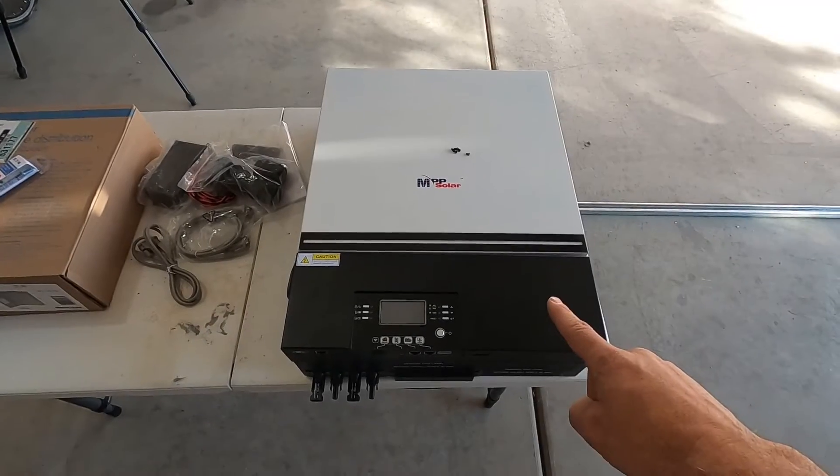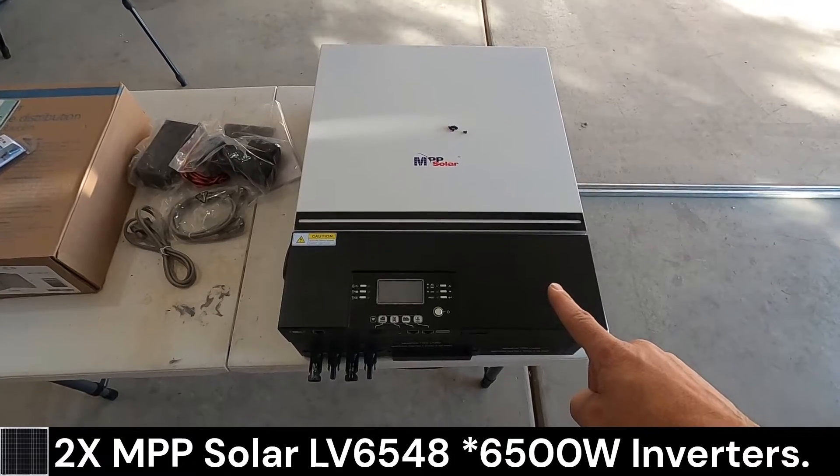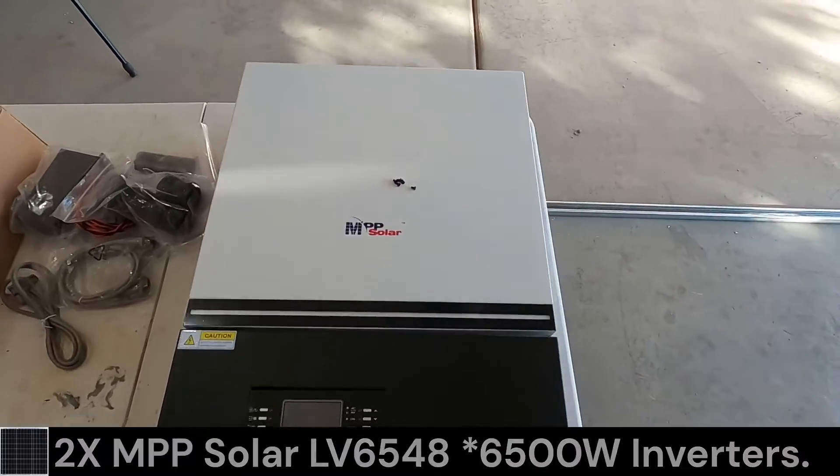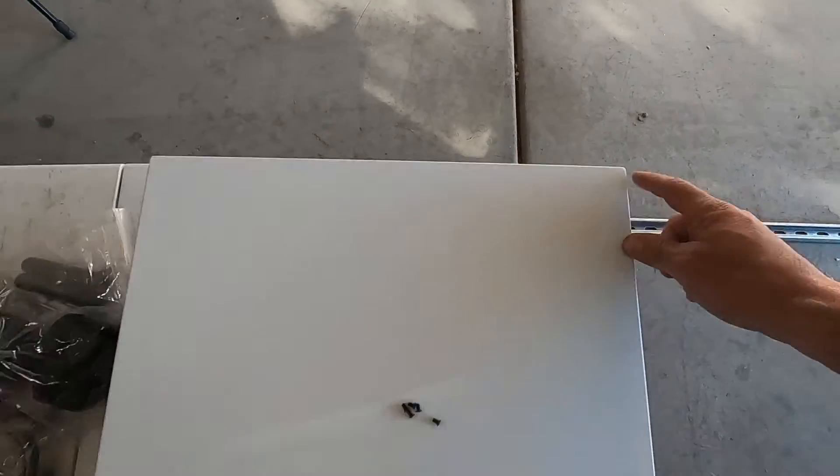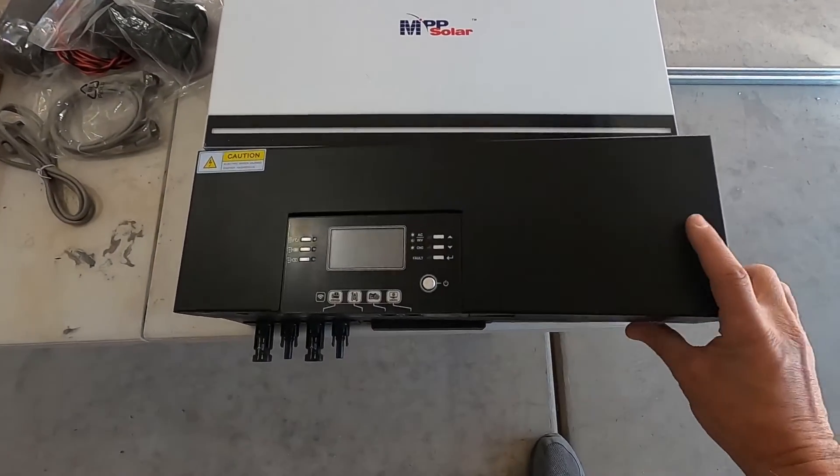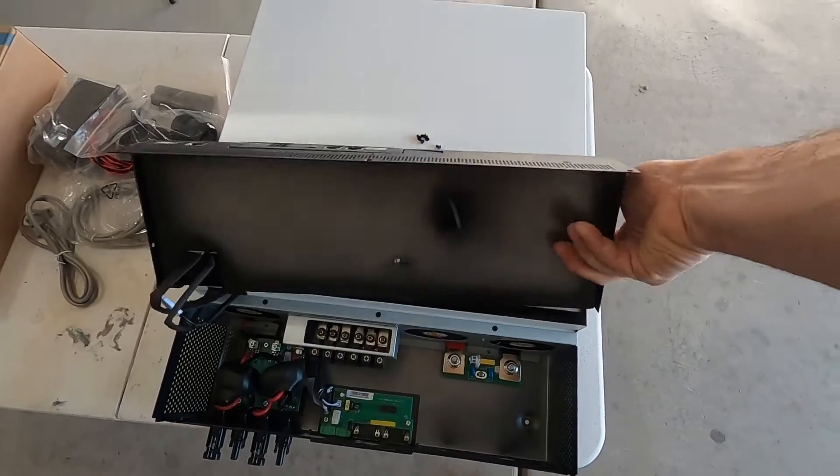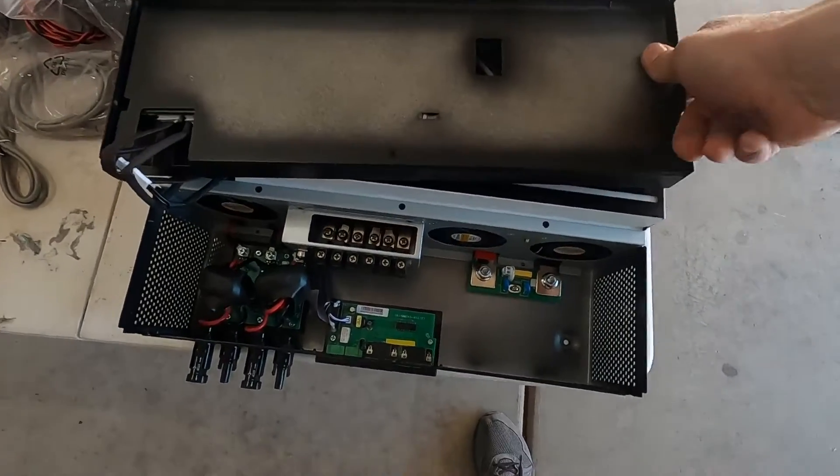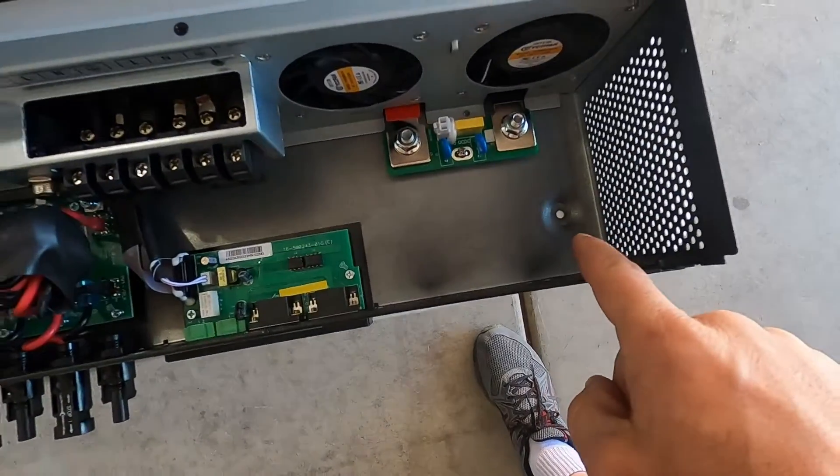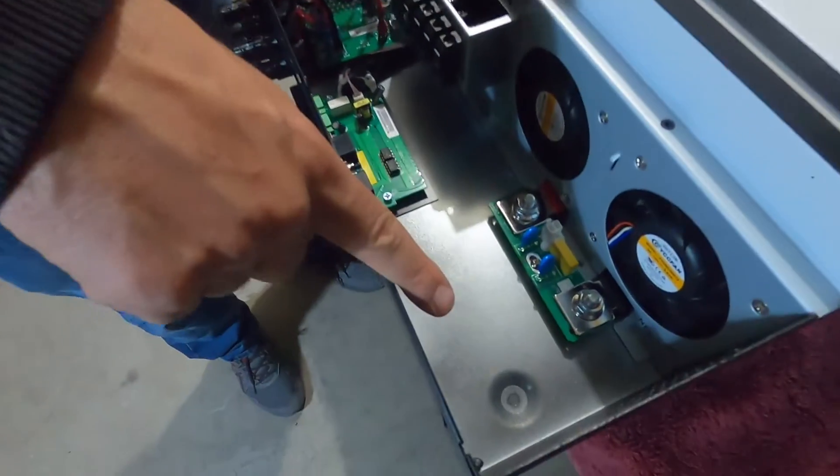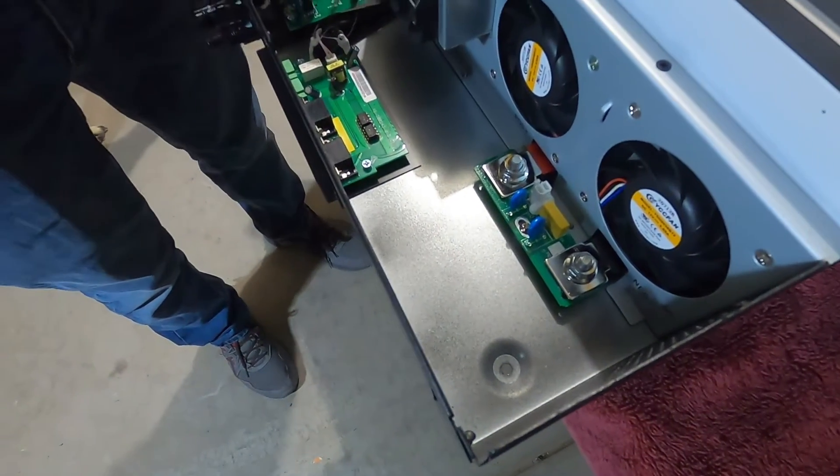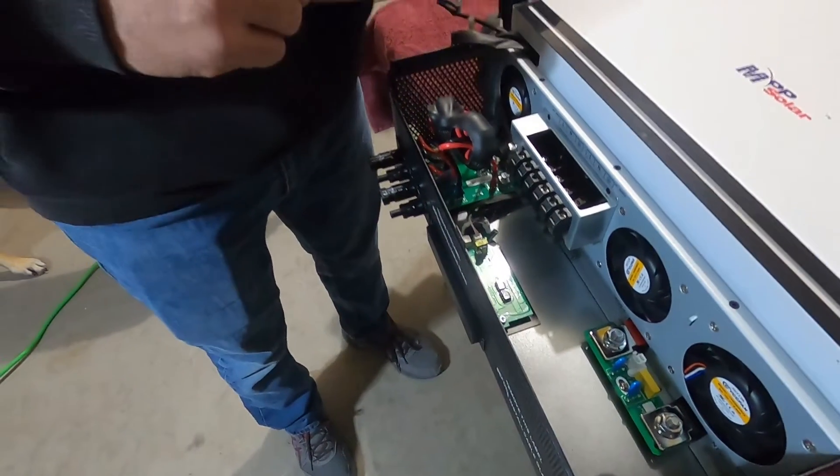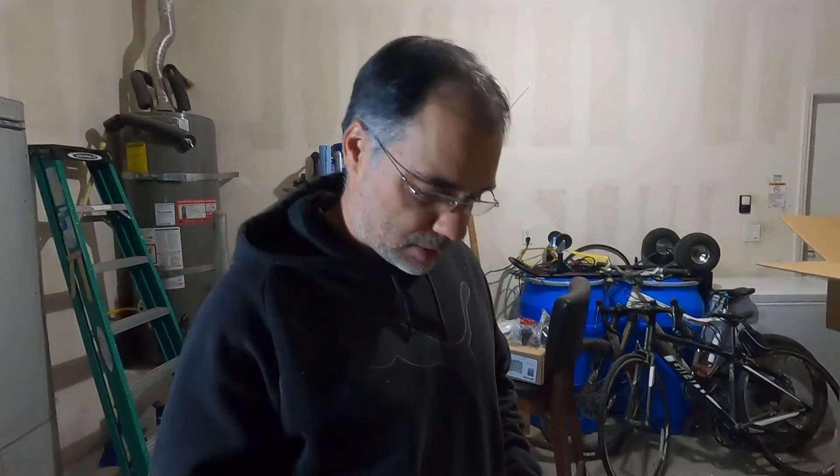So we'll be mounting two LV6548 6000 watt inverters. There's two mounting holes at the top and also two mounting holes on the inside. The mounting holes here are designed for M6 bolts, but they don't make M6 strut nuts. They only make quarter inch strut nuts, so it's slightly larger than M6. So we're gonna have to drill these holes out.